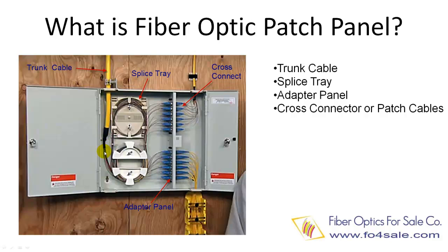Individual fibers in the cable are then fanned out and fusion spliced to individual fiber pigtails. The fusion splices are protected in the splice trays. Each fiber pigtail is then plugged into one side of the connector panel. Smaller outgoing cables or patch cables are plugged into the other side of the connector panel, so each fiber can be managed separately.